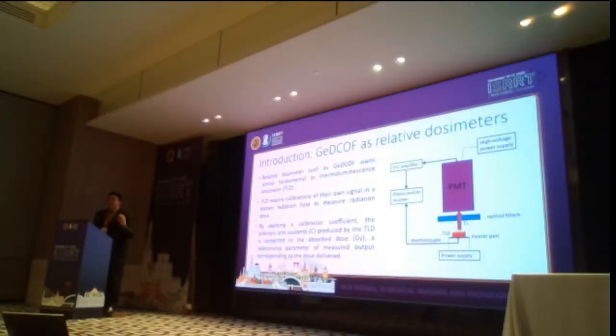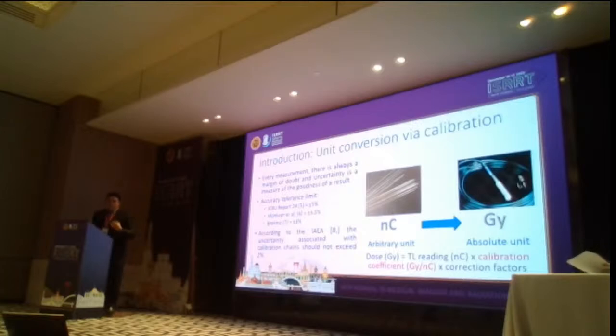The GeDCOF has a similar fundamental to a TLD, where it requires thermal stimulation in order to acquire the signal. The measurement of the radiation dose coming from the GeDCOF is very important, especially for the radiotherapy dosimetry system, where we need to quantify the arbitrary unit coming from the GeDCOF and convert it into the actual dose. That's why we need to do a calibration for the relative dosimeter, and then we will get the actual dose. So basically that's what we are doing, the cross-calibrating. That's the image of the optical fiber, the raw material for the relative dosimeter, and then we cross-calibrate using the ionization chamber, the gold standard, particularly for the radiotherapy measurement.